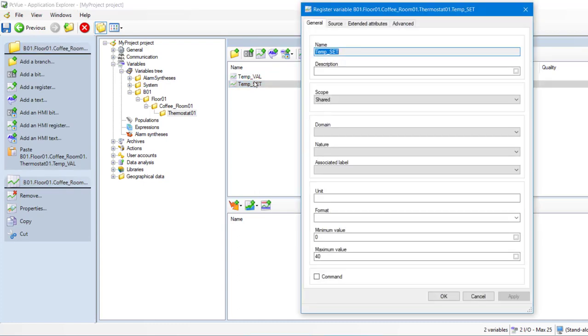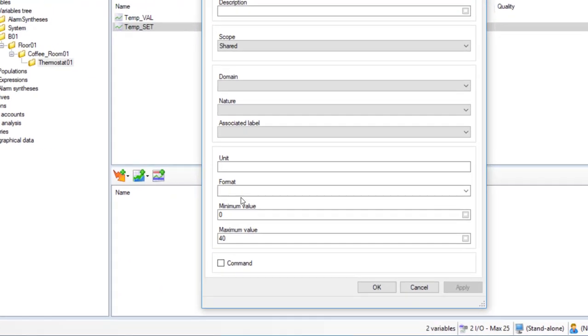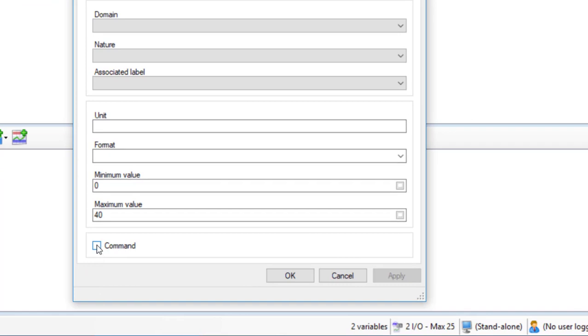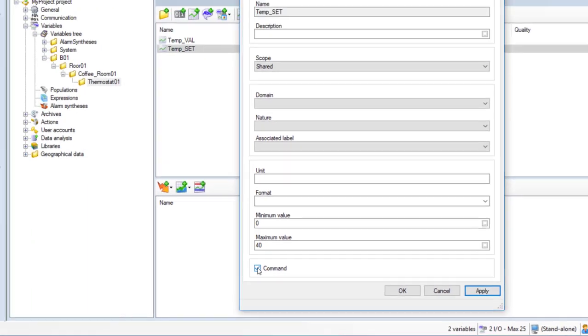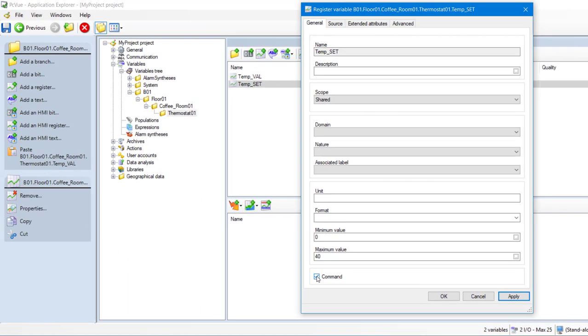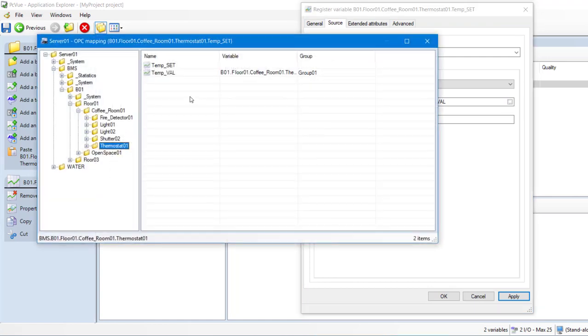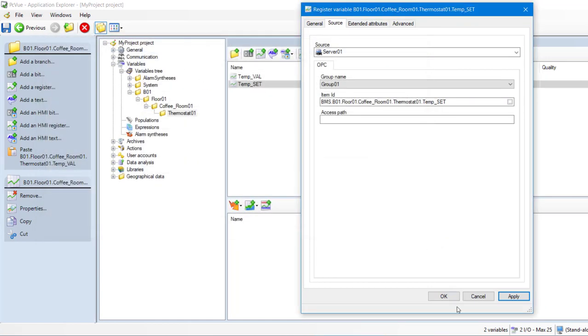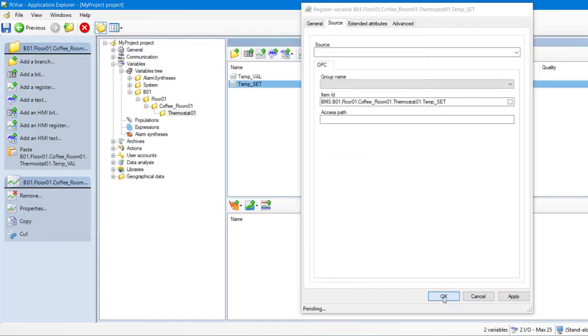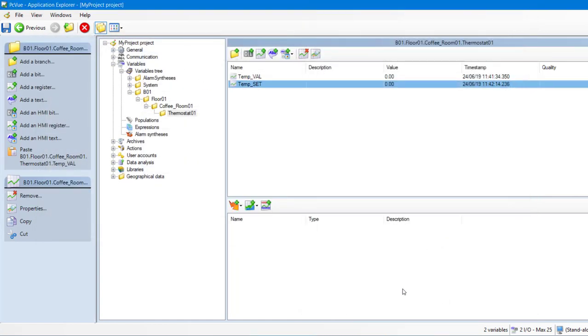As we are going to control the thermostat from the HMI, we must set the command property. It is used to determine whether a variable can be set by PCVue or not. We also need to change the ID of our variable. That's it, our variables are created.